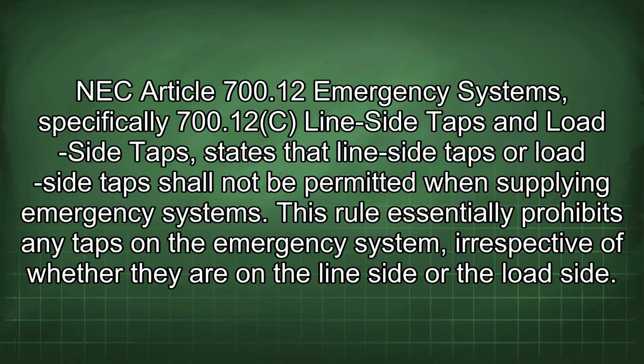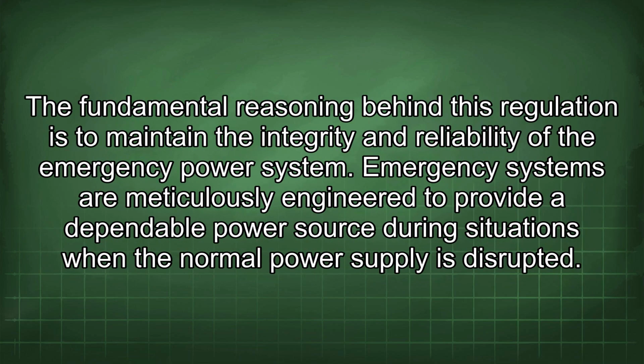NEC Article 700.12, Emergency Systems, specifically 700.12(C), line-side taps and load-side taps, states that line-side taps or a load-side tap shall not be permitted when supplying emergency systems. This rule essentially prohibits any taps in the emergency system, irrespective of whether they are on the line side or the load side. The fundamental reasoning behind this regulation is to maintain the integrity and reliability of the emergency power system.